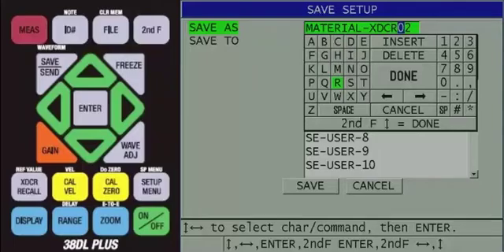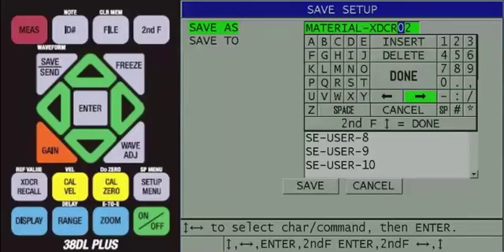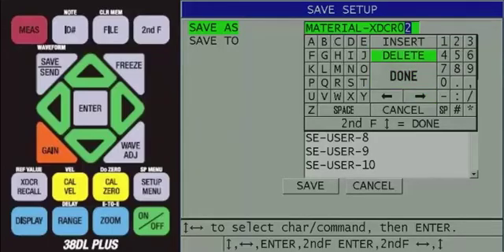Once you have finished entering the name of the custom transducer setup, use the arrow keys to highlight the right arrow, then keep pressing the enter key until the last character on the save as line is highlighted. Then use the arrow keys to highlight the word delete, and keep pressing the enter key to delete any unwanted characters.